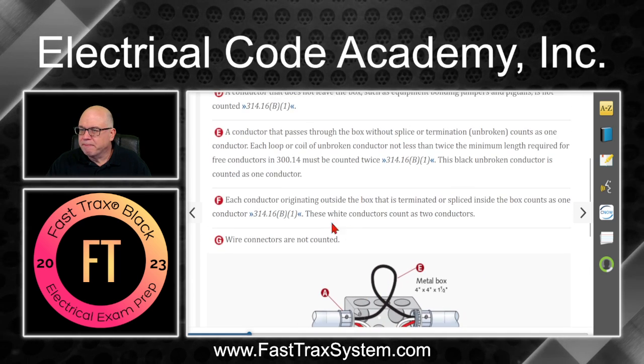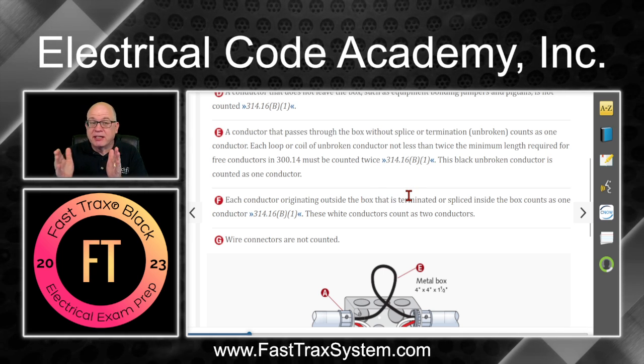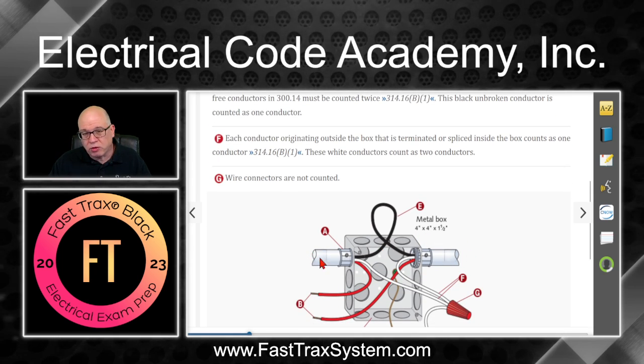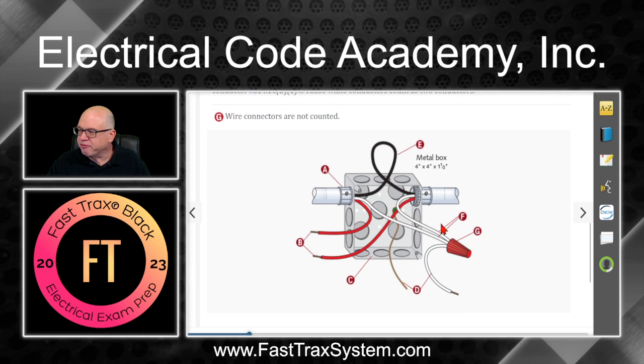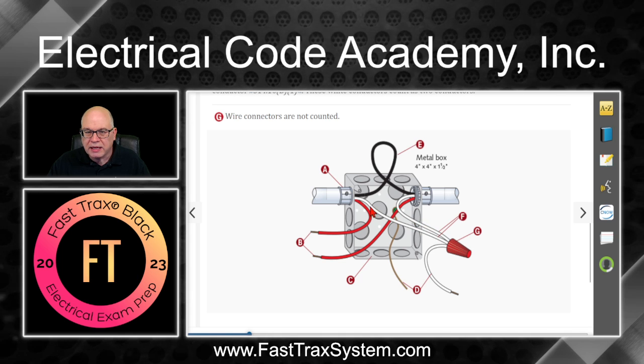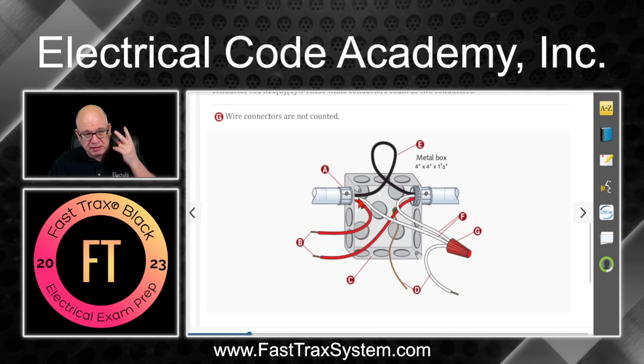E shows a conductor passing through the box. A conductor that passes through the box without a splice or termination, unbroken, counts as one conductor. If the loop were twice the free conductor requirement — which is six inches per 300.14, making it 12 inches — then it would count as two conductors. But since it's less than 12 inches, we only count it as one. F covers the grounded conductors — the white wires. Each conductor originating outside the box that is terminated or spliced inside counts as one conductor. So one coming from this direction and one coming from the other direction — even though they're spliced together in the box, each one counts as a conductor. So you have two of them.